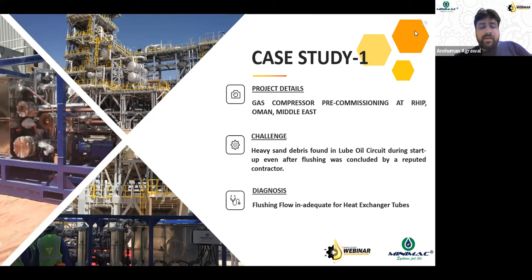But they also forgot the fact that these heat exchangers were subject to a sandy environment for a very long time while they were kept in the yards. And probably the ports were open. So a lot of sand got deposited in the internals of the heat exchangers. And as they were not flushed during the plant pre-commissioning activity, as soon as the system was started, the entire sand which was deposited in the internals of the heat exchanger started getting off and collected in the gas compressor lubrication system.